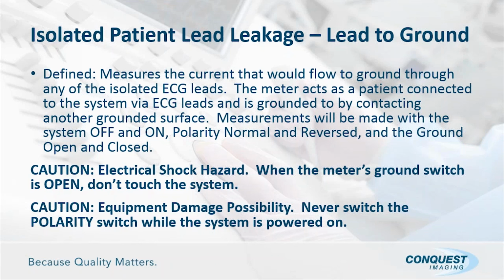So the measurements, again, will need to be made with the system off and on, polarity normal and reverse, and ground open and closed. It's critical that we do all these different conditions because you will see, as you do these, they do provide significantly different results. So again, we have the possibility of electrical shock. Anytime you open the ground wire or basically disconnect the ground, the system automatically looks for the next easiest place to go to ground. So if there is an unsafe condition that exists on the system, you're part of it, and you could simply get shocked.